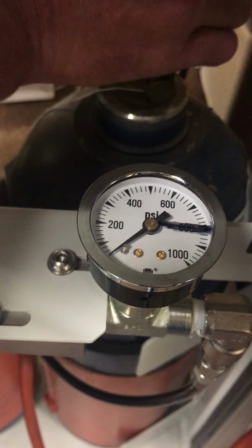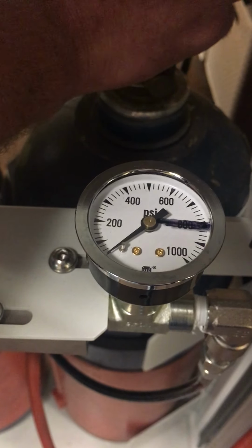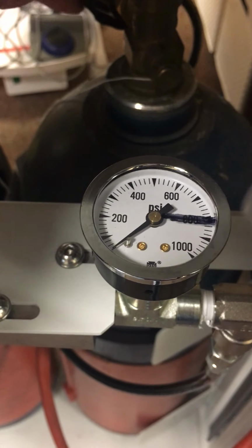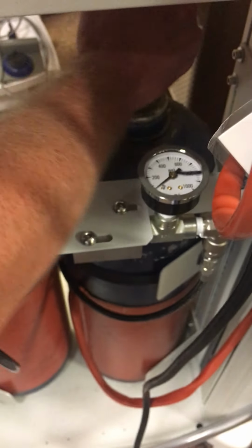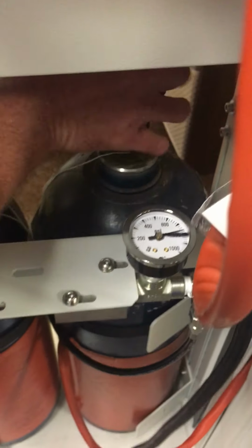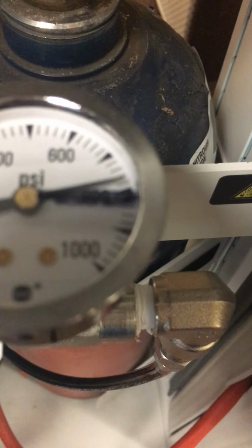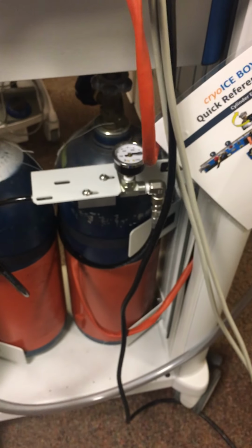We're going to go ahead and open the tank. You'll notice that the tank that I'm opening has a connection that runs from the tank itself all the way through right here into the pressure line into the generator. This is just lefty-loosey to open, righty-tighty to close. If we look here on the pressure gauge, we're right at 800. Knowing the heater blanket is connected, we will probably get more pressure.